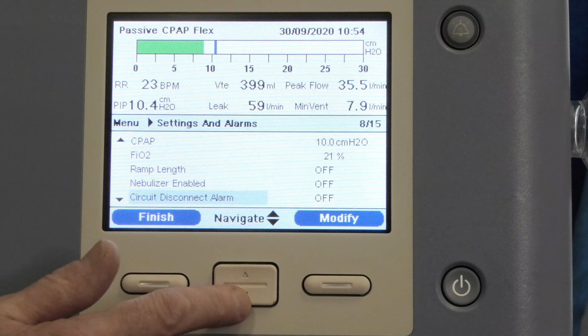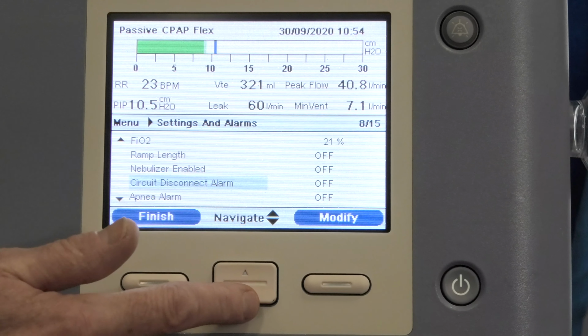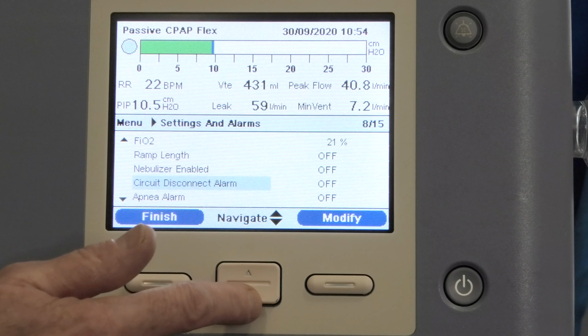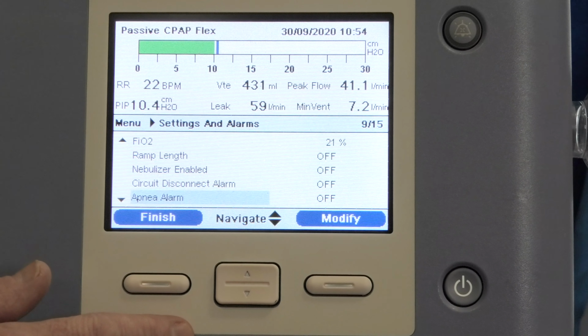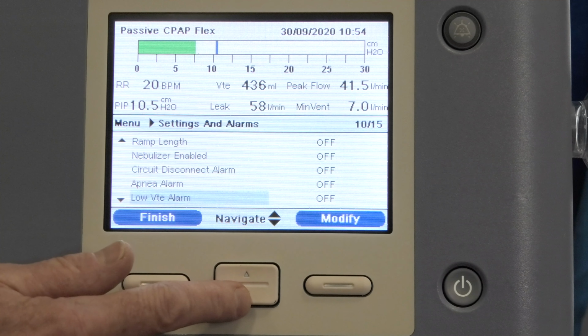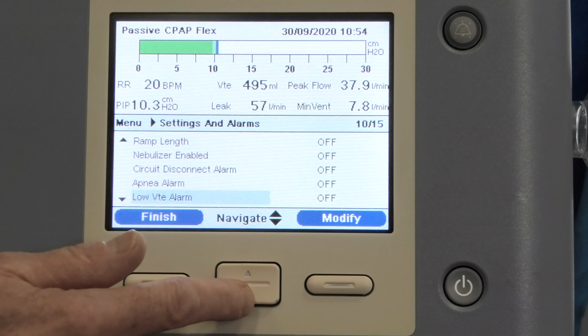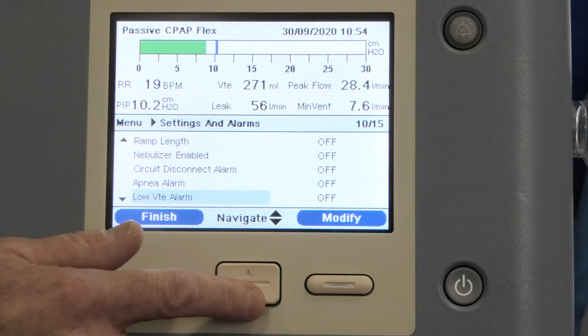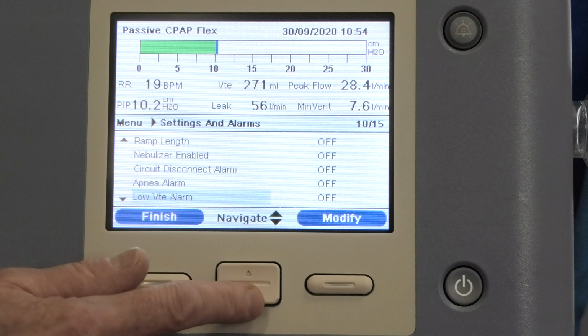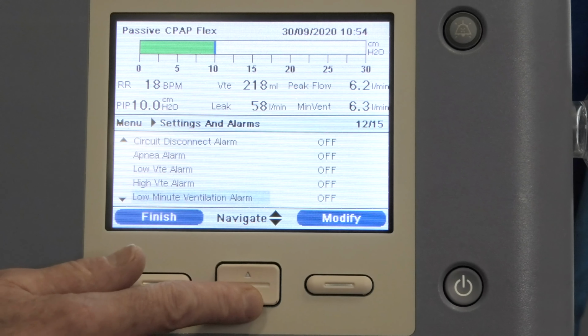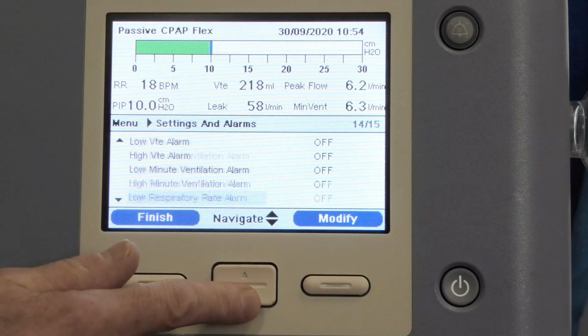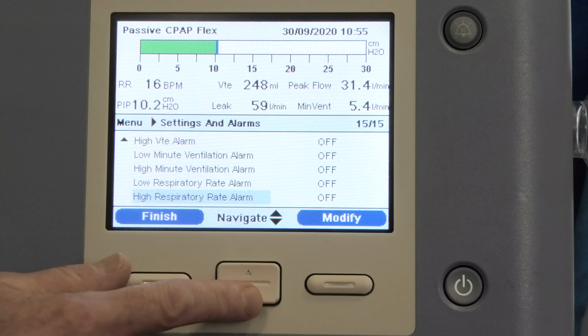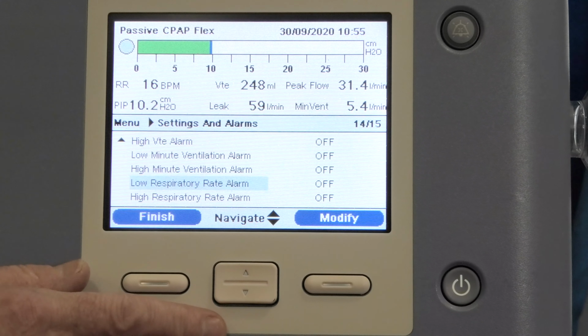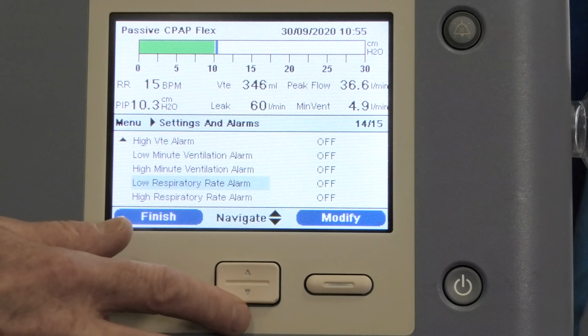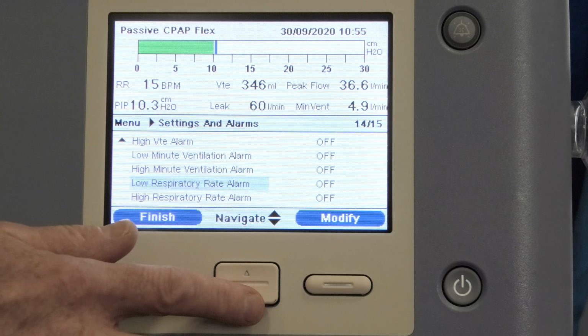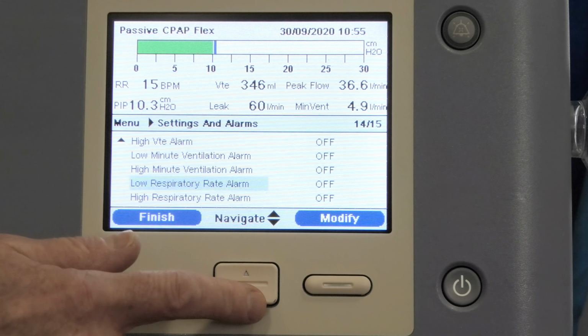We have circuit disconnect alarms and apnea alarms, which are extremely important. So we would always set a circuit disconnect alarm and we would always set an apnea alarm. Underneath you have a variety of alarms which we tend not to set because the machine alarms all the time and they're not necessary for the safe use of the machine. So we have high and low tidal volume, high and low minute ventilation. We have high and low respiratory rate. We do set low respiratory rates in CPAP patients because it's a spontaneous mode. There is no backup rate for patients on CPAP. So if they're breathing more slowly, we need to know about it.